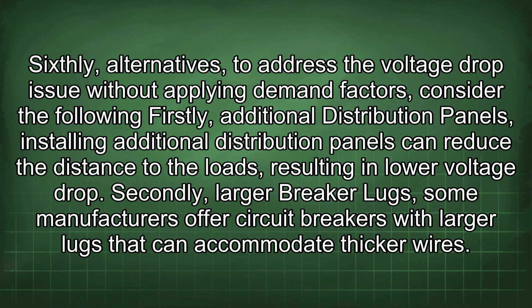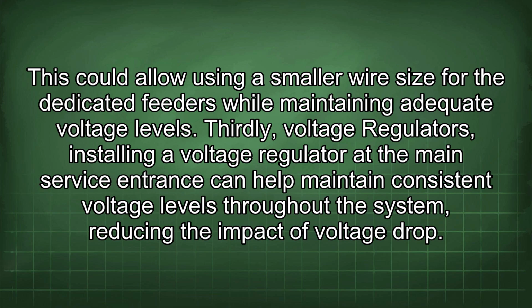Sixthly, alternatives. To address the voltage drop issue without applying demand factors, consider the following. Firstly, additional distribution panels. Installing additional distribution panels can reduce the distance to the loads, resulting in low voltage drop. Secondly, larger breaker lugs. Some manufacturers offer circuit breakers with larger lugs that can accommodate thicker wires. This could allow using a smaller wire size for the dedicated feeders while maintaining adequate voltage levels.